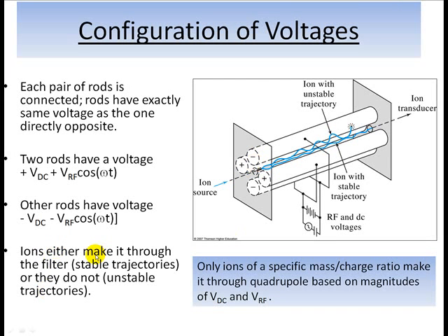And so ions, basically, they either make it through this filter and they're detected by this ion transducer, or they do not make it through the filter. Only ions of a specific mass charge ratio make it through quadrupole at any particular time.